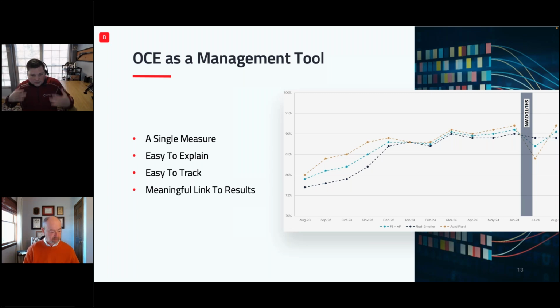And I've seen results where, when you look at OCE across an entire fleet, you can immediately see the doers and the ones that need a little more effort. OCE can be in the 80-90% range for some sites and be at 20% for others. Well, let's put some effort down there at the 20%ers and get them up. It becomes easier to explain, easier to track, and again, it's a singular number. That normalized metric, I can't talk enough about it.